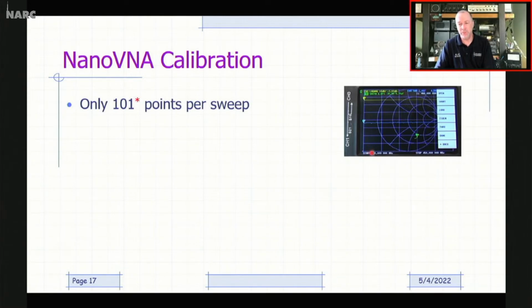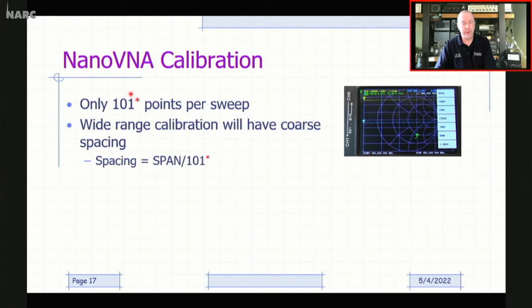You might find that the spacing between those points might go completely around a particular measurement band that you want to measure. For example, on the HF frequency band, if you measure from 2 to 30 megahertz with 100 points, you might only get 1 or 2 points that land within our HF bands that we can use, and you're not going to get a very good calibration for that. Now, I put an asterisk here because there are later versions of firmware that do increase the number of measurement points, but it's generally to 200 to 400. That still could be fairly coarse depending on what frequency range you're measuring over.